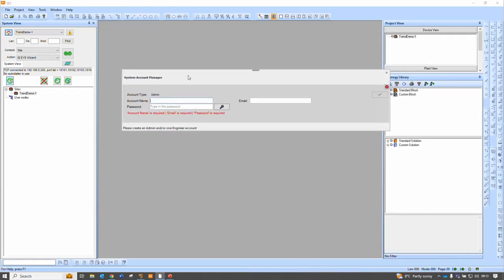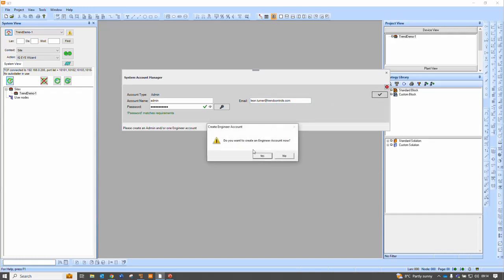Now, this is very different. So now I'm setting up a system account. This system account will be synchronized throughout the entire system, be that two controllers or a thousand. So I do not have to go through and add individual users to every single controller, which is the way we used to do this and still do in IQ4. So now I need to type in a password. I'm going to make that nice and simple. These are not recommended values at all and type in an email address. It has to be a valid email address for reasons I'll explain in a little while. So that is all good.